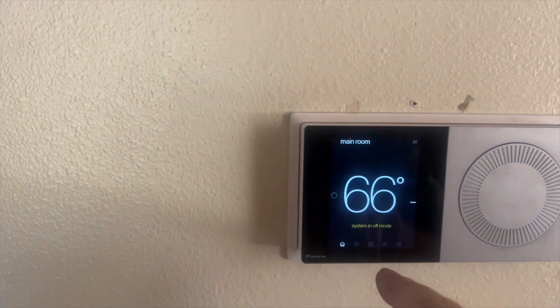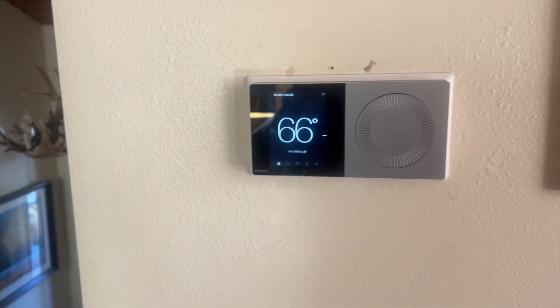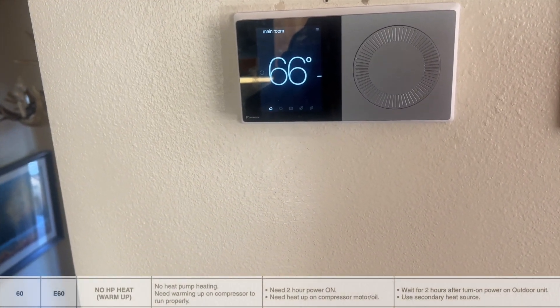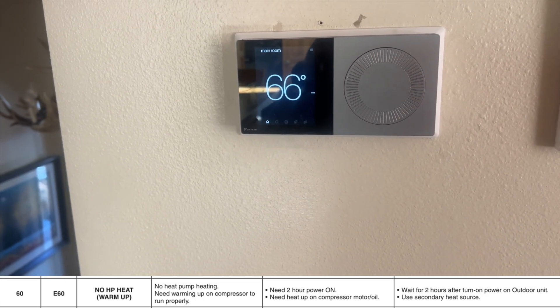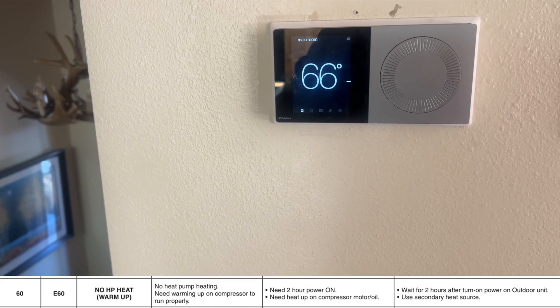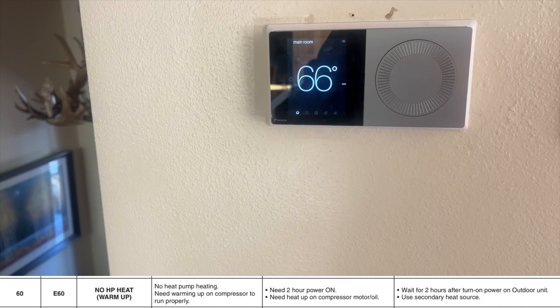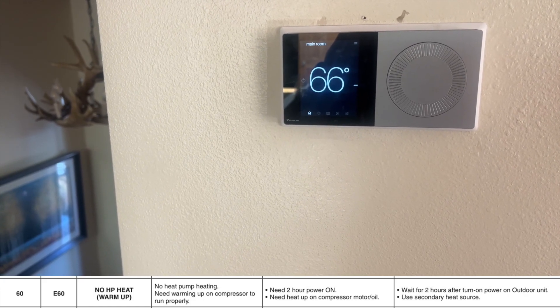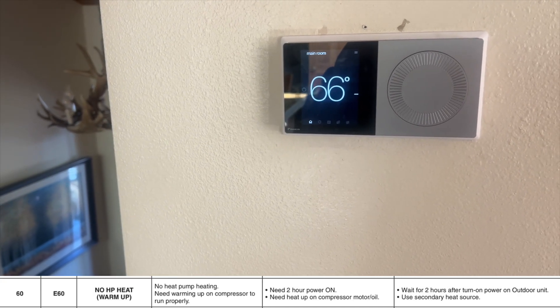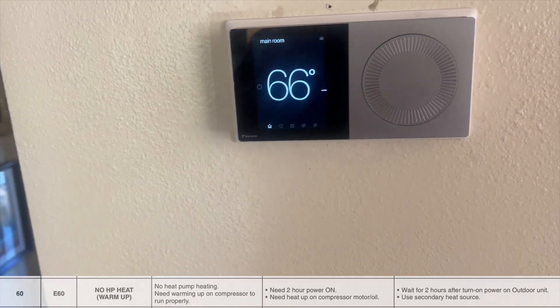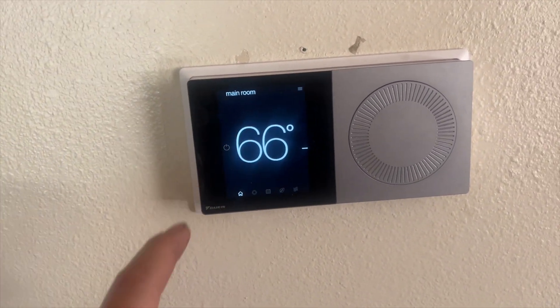I put it in heat mode and it did nothing, but then the outdoor unit gave a code of E60. E60 means no heat pump heating — compressor needs warming up to run properly. You need two hours of power-on time for the compressor to heat up. After turning on power to the outdoor unit, use a secondary heat source.